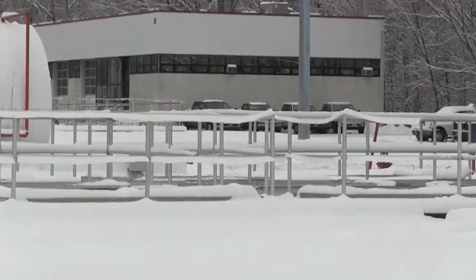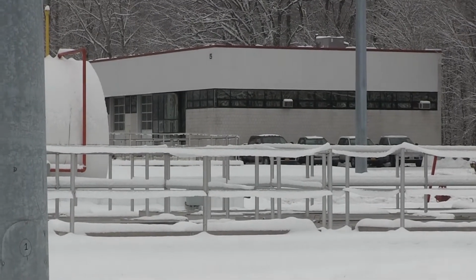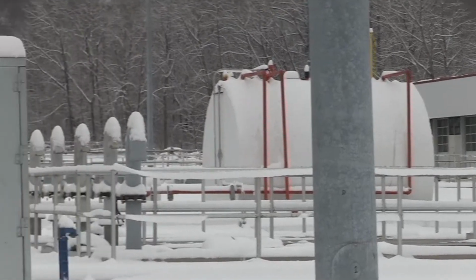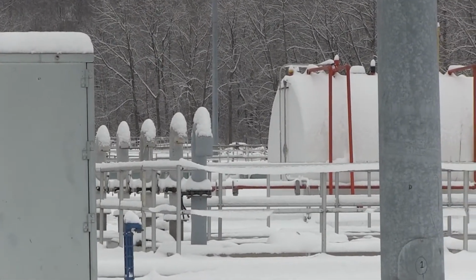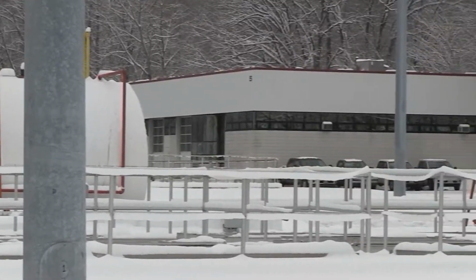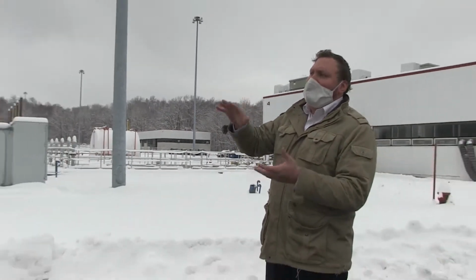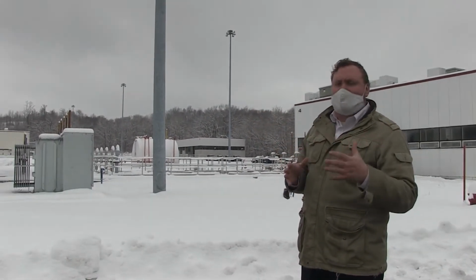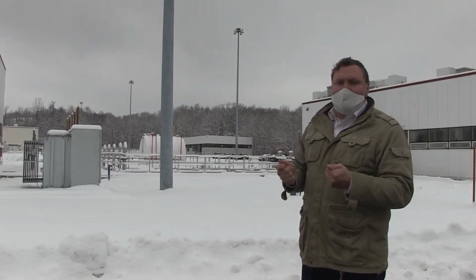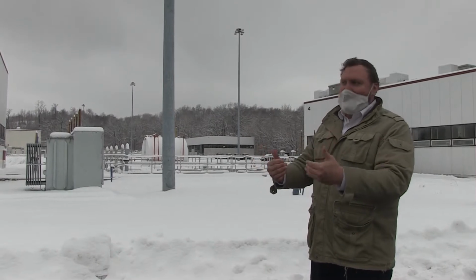But those channels you see with the railing and the vent pipes on the end, just past that black corrugated pipe. Basically, the goal of those is to slow down the water coming in to about 1 foot per second, 0.8 feet per second. What that does is it allows the grit and those heavier materials that I have mentioned to fall out, but it keeps the organics suspended, right? So it's all about specific density as you move the water forward.